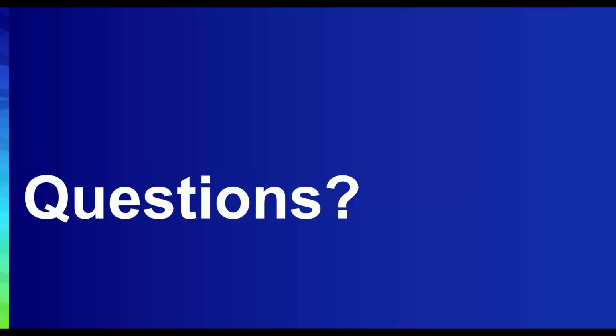Okay, thank you. Another one, can you explain the difference between UL and ETL listings? Is one better than the other, or why is one chosen over the other? So I had touched on many of the standards being ANSI standards. ANSI standards mean that is a test standard that can be used by any accredited laboratory. ETL and UL, as well as many other global accredited laboratories, use those ANSI standards. So in theory, those test protocols and processes to get a UL or a BSI or an ETL approval should be following the same protocols laid out in the ANSI standards.